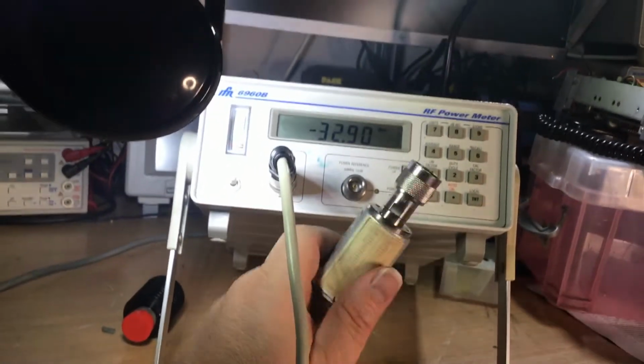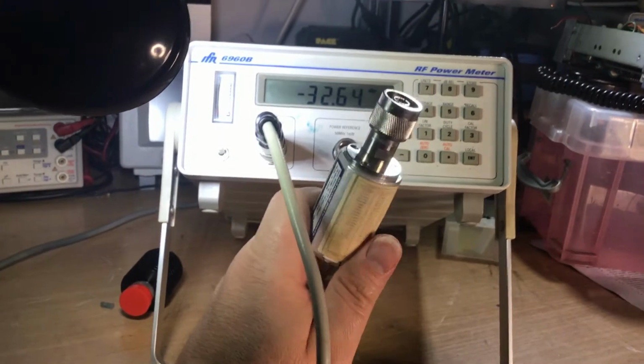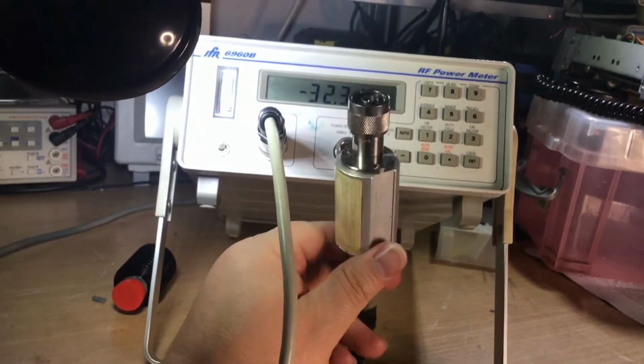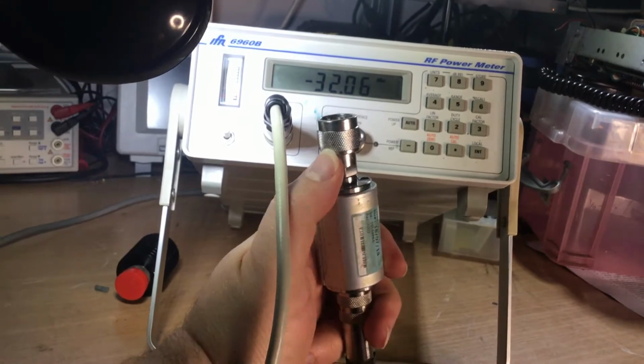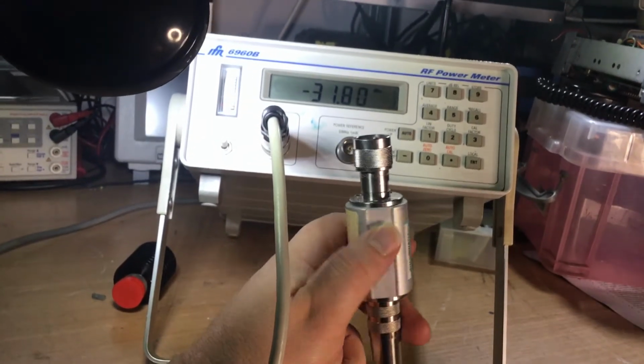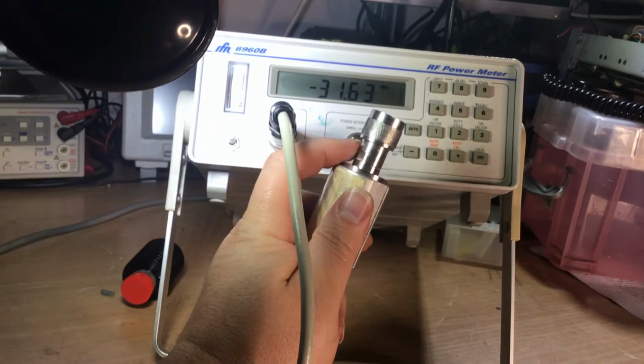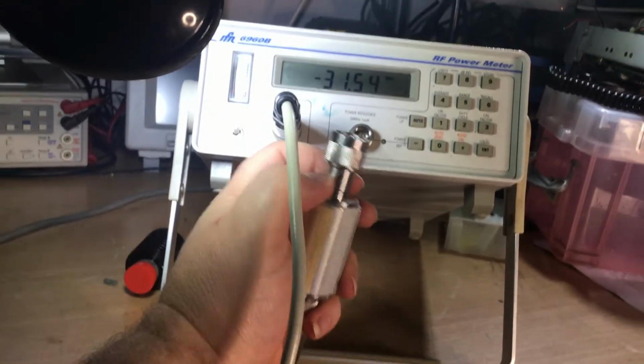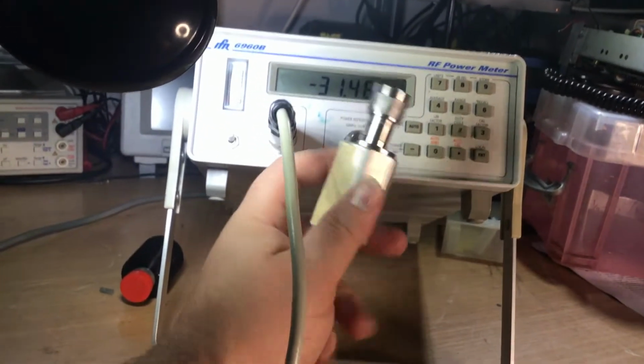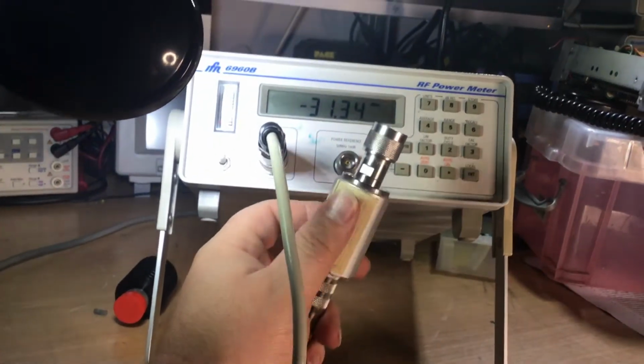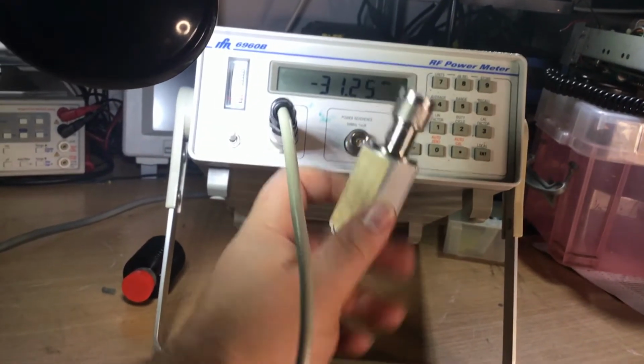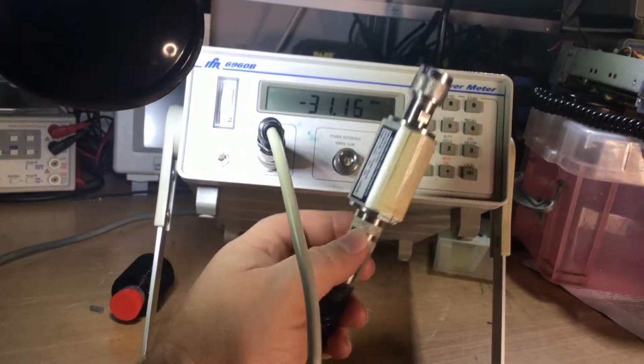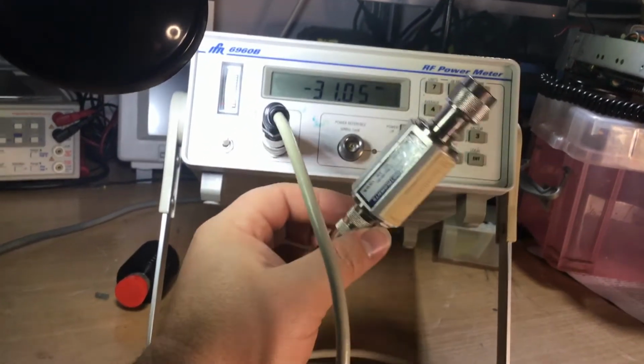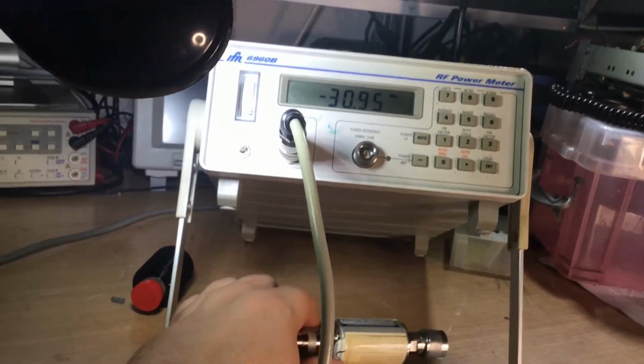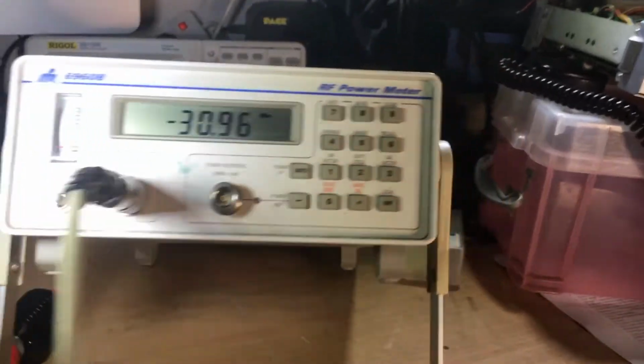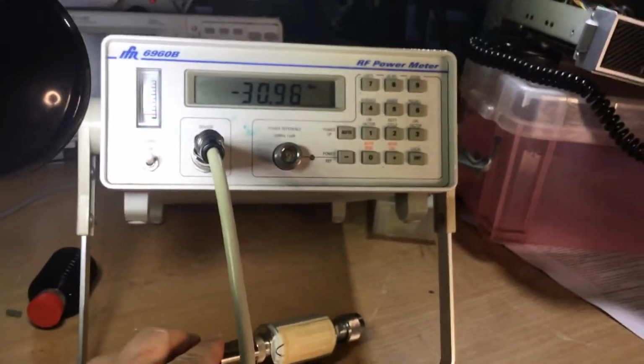I have done repairs on these sensors under microscope, and I'll do a video on what's inside these, because the power handling and measurement circuitry is built into the N-type socket here in that neck, and the 2 gold wires that come out which connect into the circuit board, and all the intelligence is basically in there. And they are very delicate, so you've got to be so careful not to damage those. Otherwise, you can lead yourself into a very expensive situation.